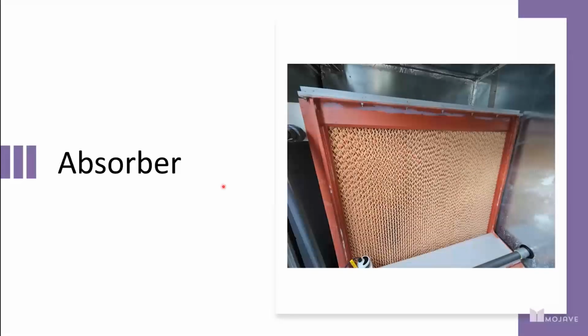So how are we interfacing liquid desiccant with the airstream? That's through this humidity absorber here. It looks somewhat like an evaporative cooler, but is very much not. Frankly, it's doing the exact opposite of an evaporative cooler. What we're doing is an impregnation style falling film, and you basically have milliliters per minute flow rates of liquid desiccant running down these channels while the air passes through this media.